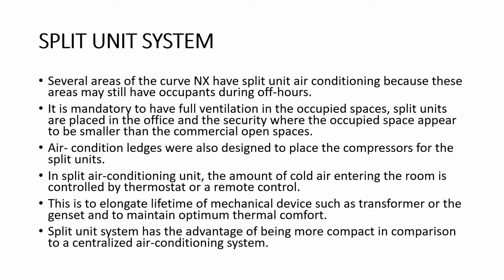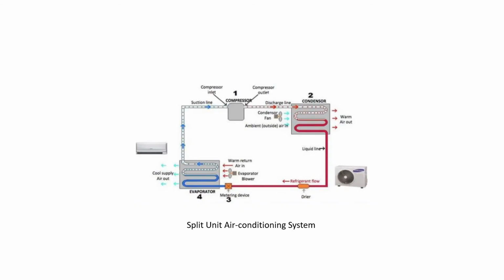Split unit system. Several areas of Curve NX have split unit air conditioning because these areas may still have occupants during off hours. It is actually mandatory to have full ventilation in the occupied space. Split units are placed in the office and the security, where the occupied space appears to be smaller than the commercial open spaces. Air conditioning ledges were also designed to place the compressors for the split units. In a split air conditioning unit, the amount of cold air entering the room is controlled by a thermostat or a remote control. This is to elongate the lifetime of mechanical devices such as the transformer or the genset and to maintain optimum thermal comfort. Split unit system has the advantage of being more compact in comparison to a centralized air conditioning system. So this is the diagram showing the split unit air conditioning system.